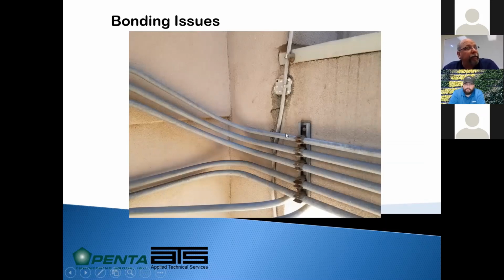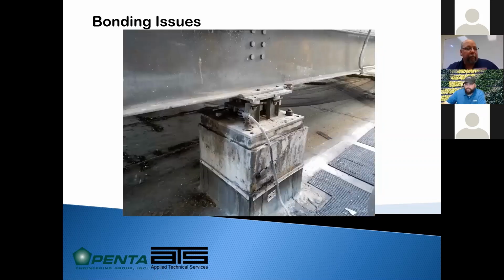Grounded metallic bodies, anything that shows continuity with the building electrical grounding or the lightning protection grounding, we need to install an equipotential bond that creates a pathway to prevent those ion differences from building up, so we don't create an area where it's going to try to create its own leader and jump off and arc into other areas. So generally within 6 feet of the conductor, anything that's a grounded metal body, we need to bond to the lightning protection system. It is a physical connection. Usually it's smaller diameter, smaller gauge than the lightning protection conductor, but it keeps those energy differences from building up. So here we'd have little small clamps with a smaller wire connection to make sure the energy is not going to jump from our down conductor to the electrical conduit and find a different pathway into the building.